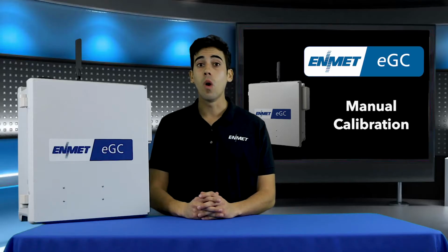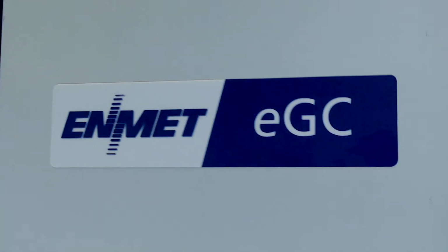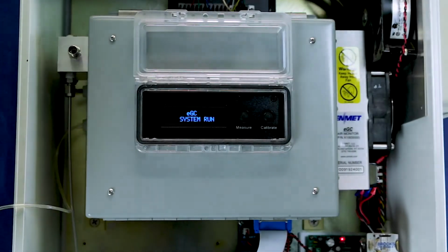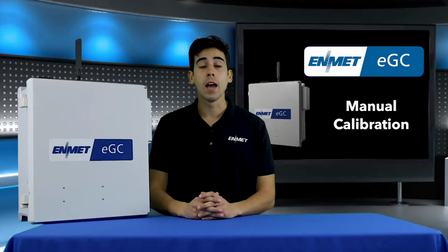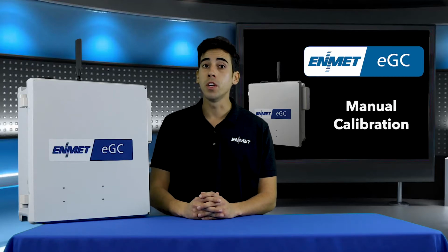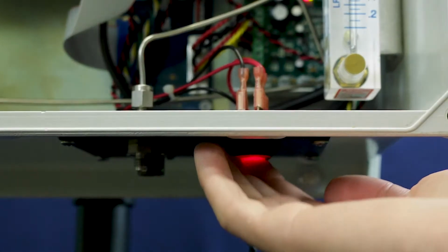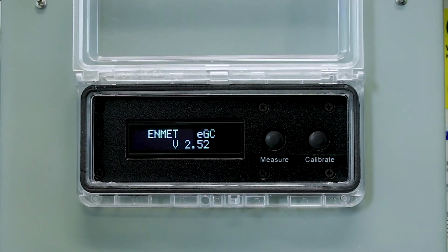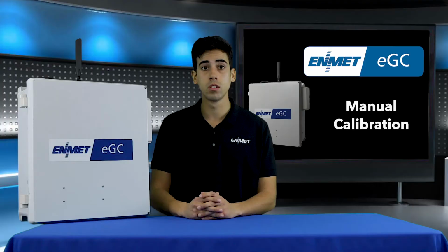This video will walk you through the manual calibration process of ENMET's eGC. A manual calibration should only be attempted after you've fully warmed up your eGC unit. To warm up your unit, turn it on by pressing the power button. The eGC will then display a startup screen and begin collecting air samples for analysis at 10-minute intervals.